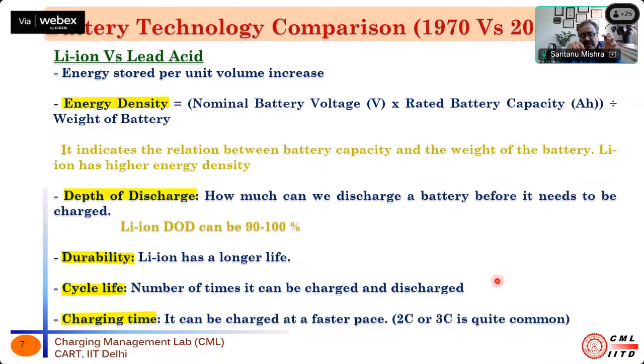If I charge a 30 kilowatt hour battery at C, that means charging at 30 kilowatt, I will take 1 hour to completely charge the battery. If I'm charging the same battery at 2C, that's 60 kilowatt, then the charging time will be half an hour, because 30 kilowatt hour divided by 60 kilowatt means I take half the time. And if I charge it at 3C, then I will take 20 minutes, because at C it takes 1 hour, and at 3C it takes 1 by 3 of an hour.